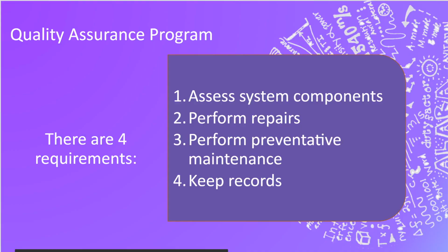Now, a quality assurance program is going to have 4 requirements. The first one is that we need to assess the system components. So there isn't much of a quality assurance program if we don't make sure that our machine is in quality operation. So we want to make sure that we're going through all the system components, making sure all the transducers work, making sure the keyboards work, the knobs, the articulating arm of the display, that the CD-ROM works, the USB works, the wheels work, the locks work, all of it needs to be checked. And there's usually going to be a check-off list.